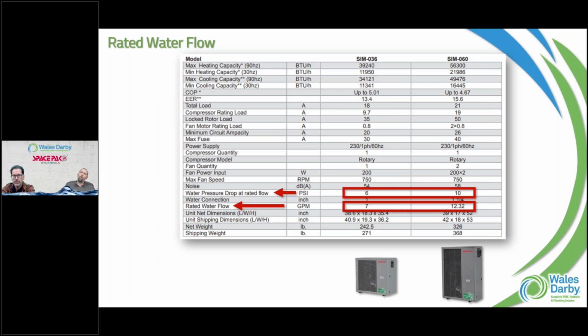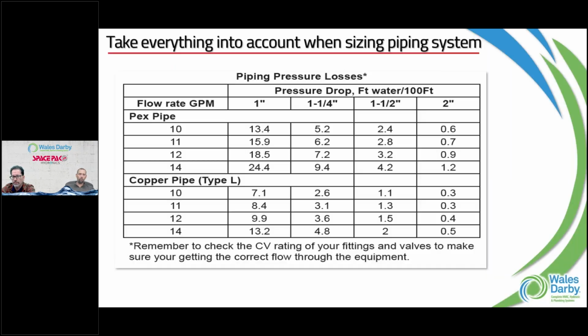That is if we used 100% water. So we just have to keep that in mind as well. If we're putting glycol in the system, which we do have to have at least a little bit of, depending on your region, even in a warmer region it's beneficial to have slight concentrations. Not so much for outdoor piping, but there is a possibility you're moving water through a refrigerant heat exchanger, and you could freeze inside there. So that's the purpose of having a little bit in there. So the pressure drop is one of the things we need when sizing that circulator, and then the required GPM, depending on the outdoor unit you're using, and depending on the piping we're using, whether copper or PEX.